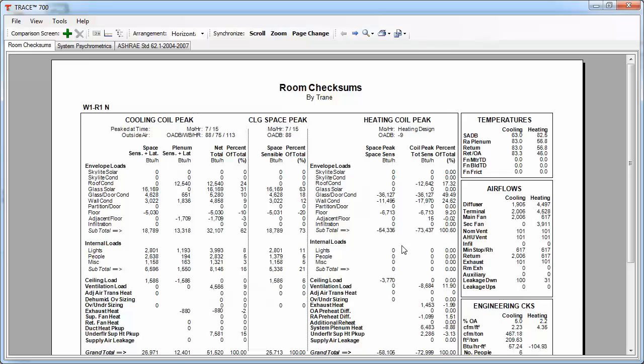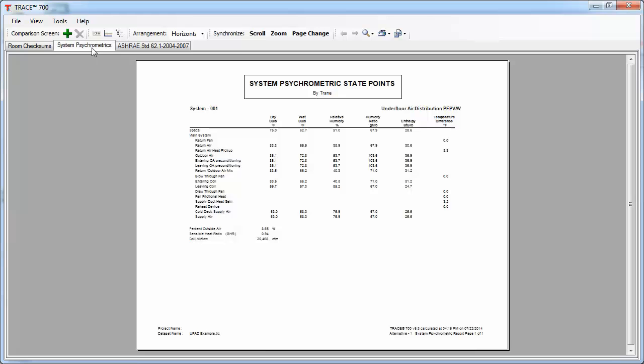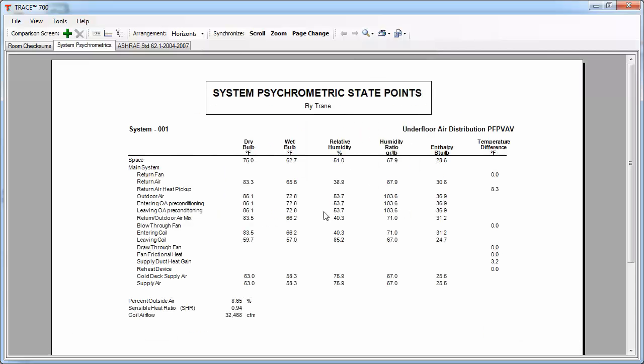There are many other outputs on this report that you can use for your UFAD system design, but I figured that those are probably the most important things you need to look at. Next, we can take a look at the psychrometrics report. This report will show you state points throughout the whole system, so you can see if your system is modeled adequately based on what the design is. These state points are going to show you what the supply or return air temperatures are, as well as what the occupied set point temperature is and its relative humidity. This report is then going to give you a basis for thermal comfort design, which is relatively important for UFAD system types, as it is a driving feature to why it's applied.